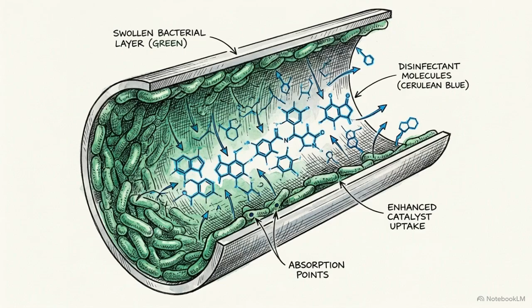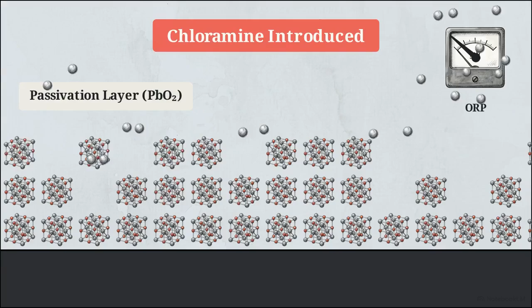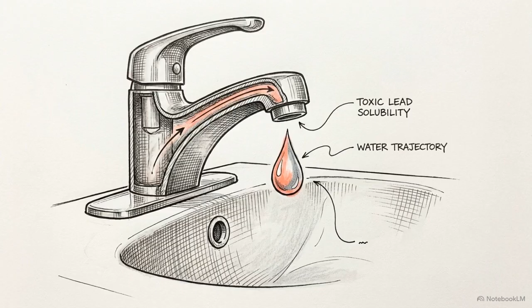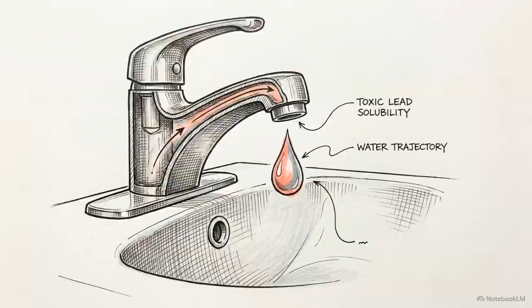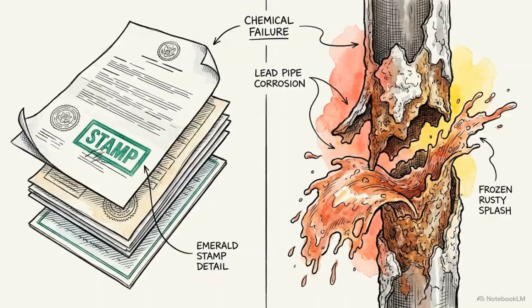For decades, the free chlorine used in DC acted as a powerful oxidant. High ORP created a stable passivation layer of lead-4 oxide inside the city's old pipes. The 2001 switch to chloramine lowered this oxidizing potential. Without a strong oxidant, that solid scale became thermodynamically unstable, chemically reducing into lead-2, a highly soluble state. This newly soluble lead dissolved directly into the drinking water supply, heading straight to residential taps. By solving a regulatory issue with a weaker oxidant, the utility unknowingly stripped away decades of essential chemical passivation.